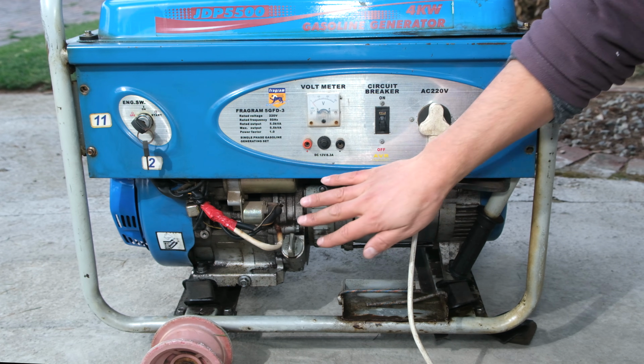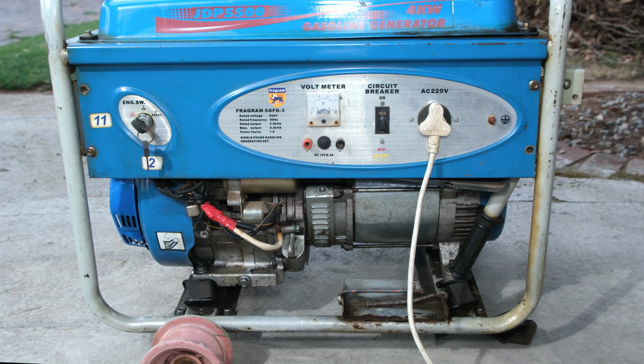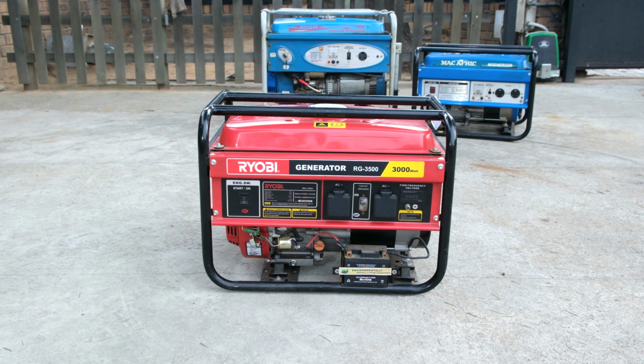When the generator is running, some of the surfaces can get very hot, and if you need to move the generator, allow it to cool down for at least 10 minutes. Generators cannot run indefinitely. That means that one has to determine how long the generator can run before it needs to be switched off to allow it to rest.